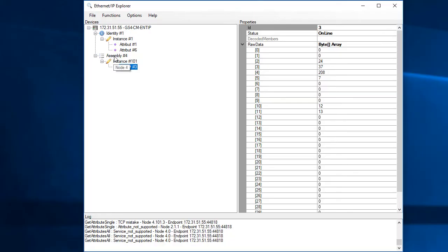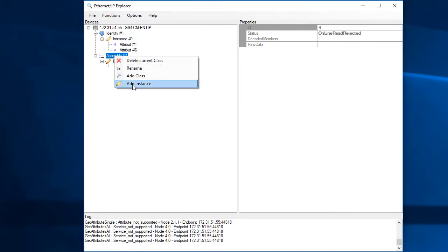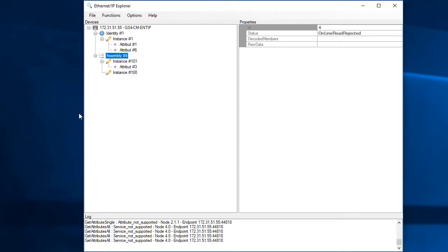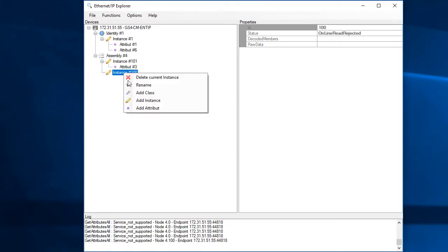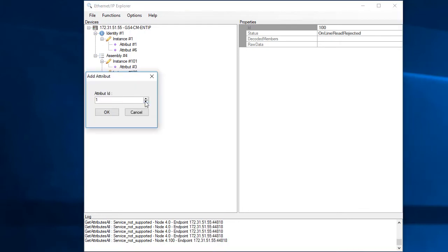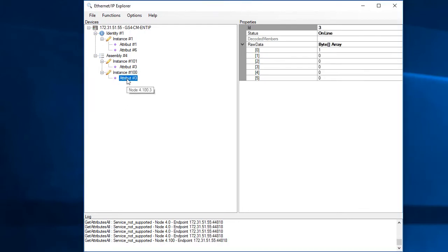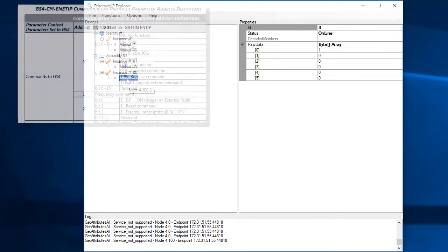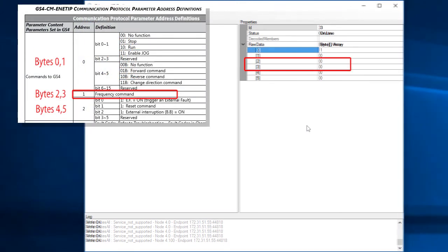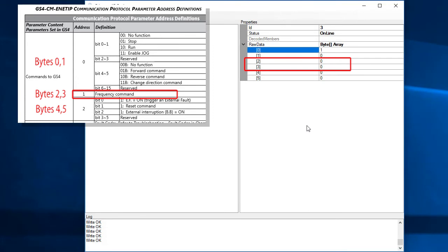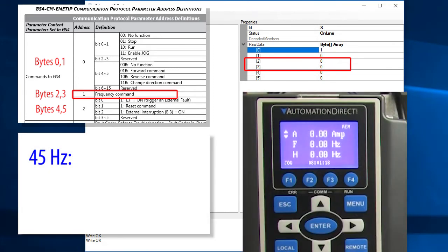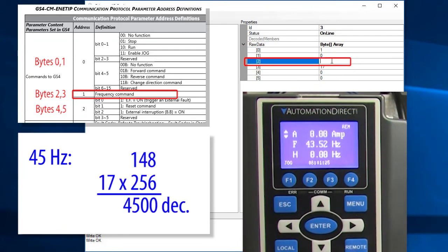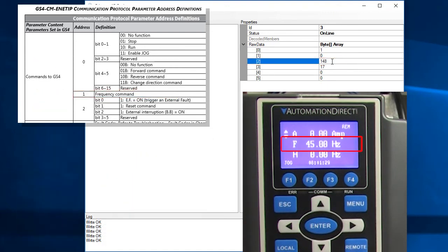Let's go ahead and open up instance 100 of the assembly class which we know from Appendix B is the output buffer so we can control the drive. Left click on the instance then right click to tell it we want attribute 3 which we know from the chart gets and sets an array of bytes. Click on that and we see the output buffer. The output buffer table says the second word – which is bytes 2 and 3 – sets the drive frequency. Suppose we want 45 Hz. There are two implied decimal places so we need a 4500 decimal – that's 17 256s and 148 1s. Sure enough, the drive is set to run at 45 Hz.